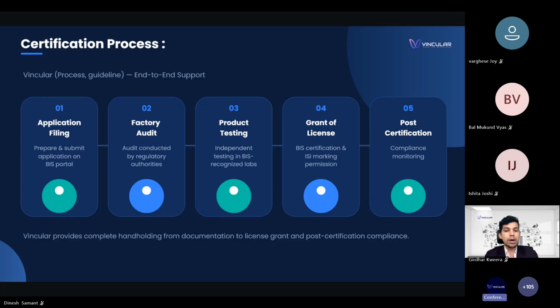Prepare the application. The manufacturer gathers all the technical documents and product details needed to apply. File the application. Once the paperwork is ready, it is submitted to the BIS portal. Factory inspection. A BIS official visits in person to check the manufacturing setup and quality control system. Product testing. The product is sent to a BIS approved lab for independent testing to confirm it meets all the safety requirements. License granted. If the documents, factory inspection, and test results all check out, BIS grants the license. Only then can the manufacturer put the ISI mark on the product.